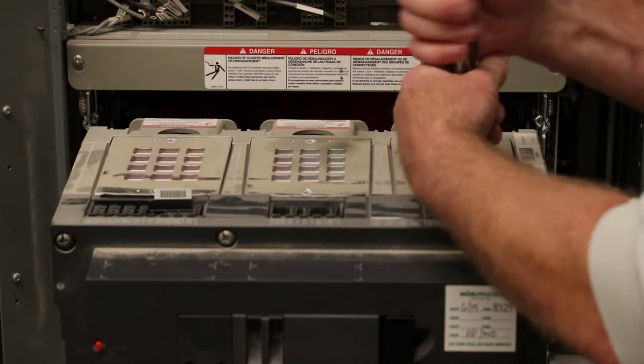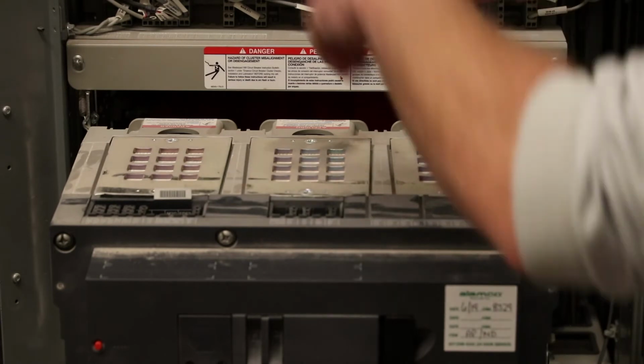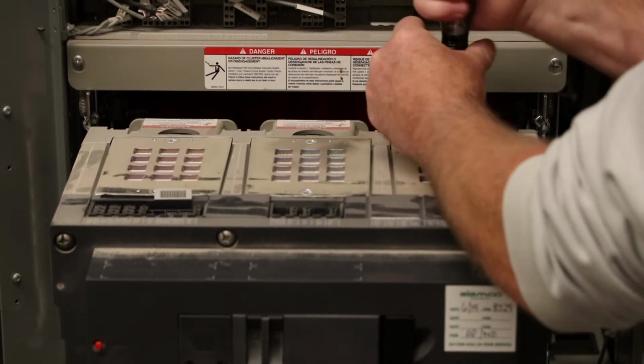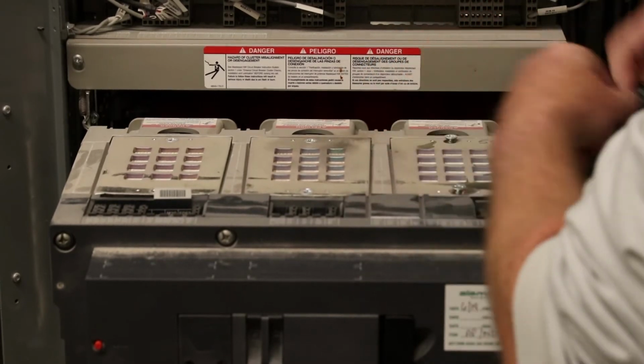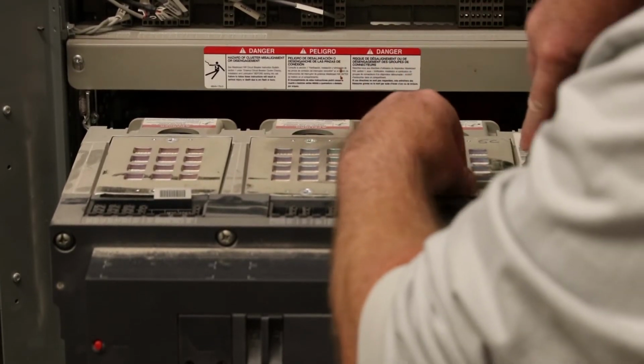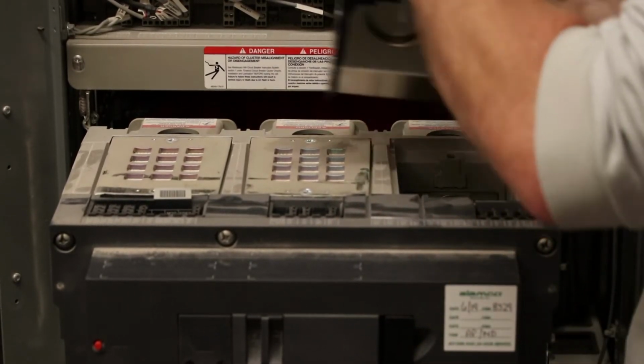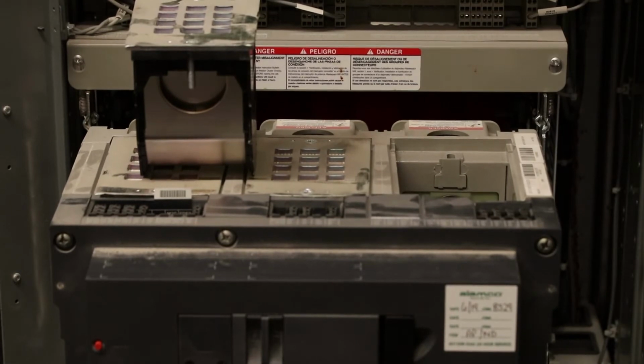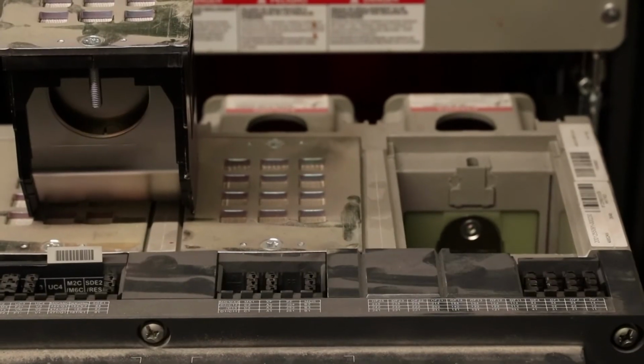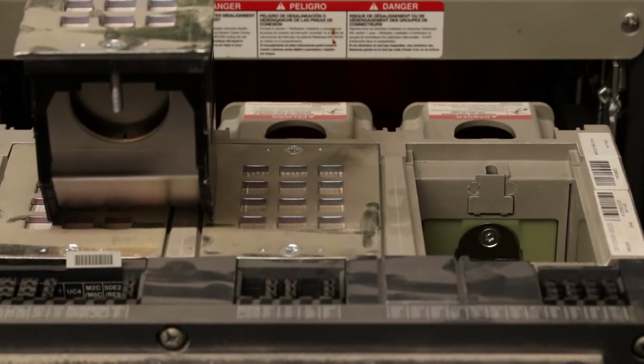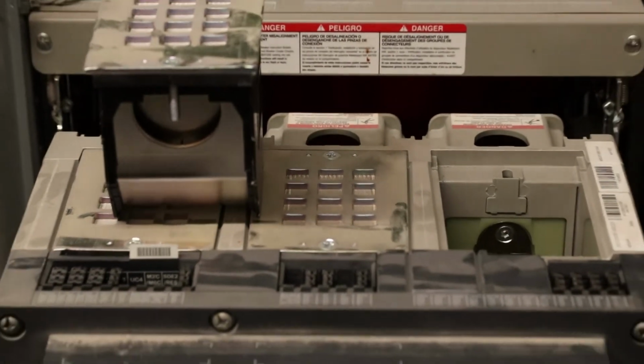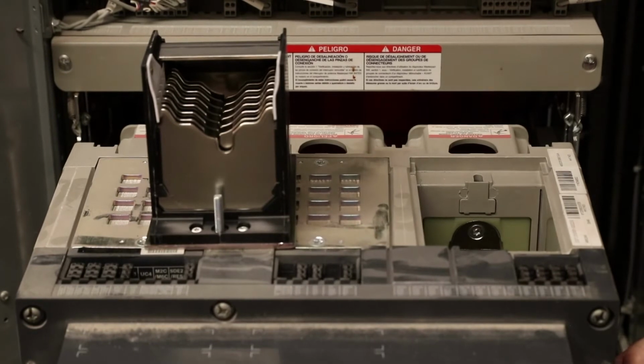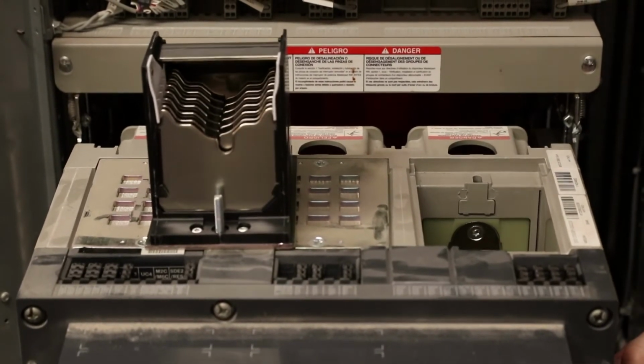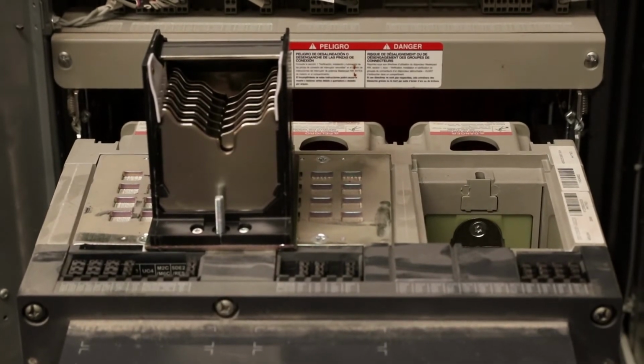These are the arc chutes. The arc chutes serve the same function as the arc chute does down on the switch back there. It absorbs and quenches the arc to prevent the main contacts from getting excessively worn. Now if you want to pop in and look at the main contacts, up here is the arcing contacts. The main contacts are down below. That's closed.